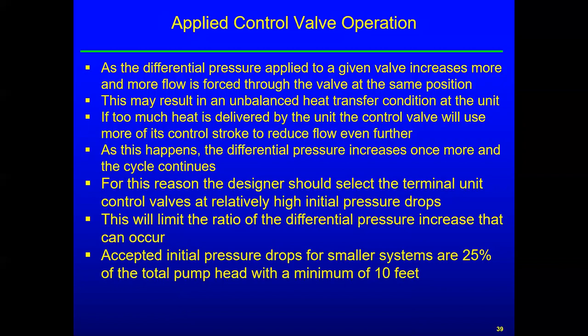So for this reason, the designer should select terminal unit control valves at a relatively high initial pressure drop. And so what that says is that we already have, even when the valve is wide open, because the valve may be downsized a little bit, it has a significant pressure drop. And so when the next door neighbor valve closes and the pressure goes up, it doesn't upset the system as much because it already has a fairly significant pressure drop across it. So that will limit the ratio of the pressure difference increase that can occur. Okay, so a lot of words and all. So you need to think through this. This last bullet is something that you need to write down and remember.